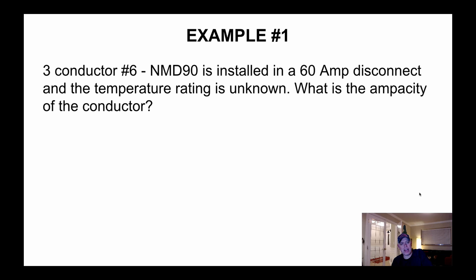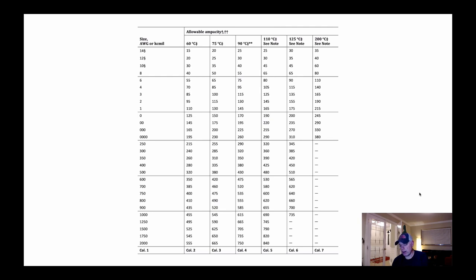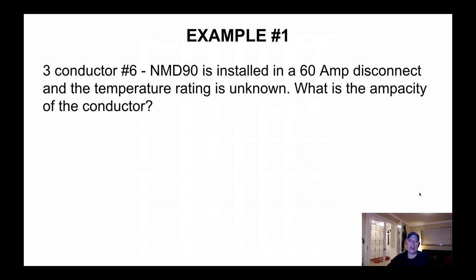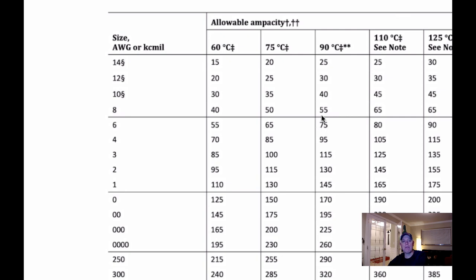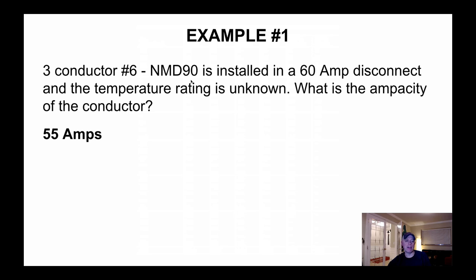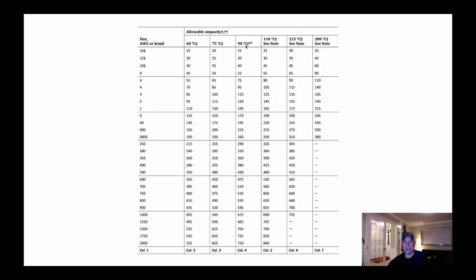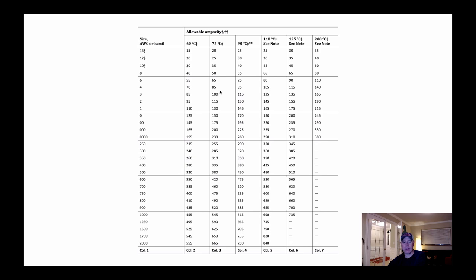Example 1: a three-conductor No. 6 NMD90 is installed in a 60-amp disconnect and the temperature rating is unknown — what is the ampacity of the conductor? Looking at Table 2, No. 6 at 90°C would be 75 amps, but because this is a 60-amp disconnect and we don't know the temperature rating, we have to base it at 60°C since it's 100 amps and below. So the ampacity is 55 amps — we use the 60-degree column, which gives us 55.